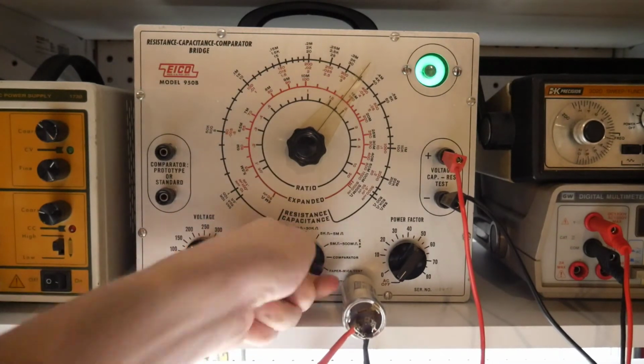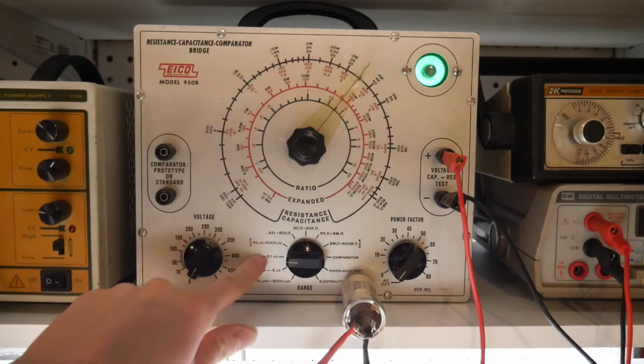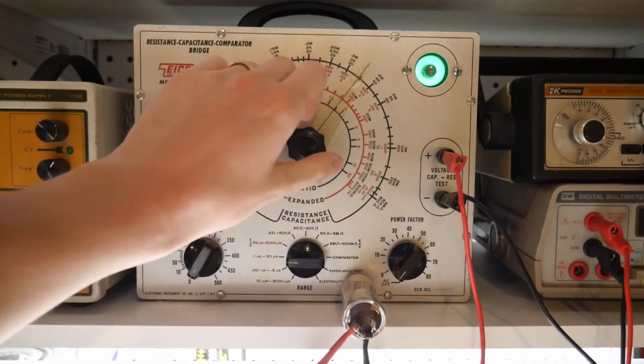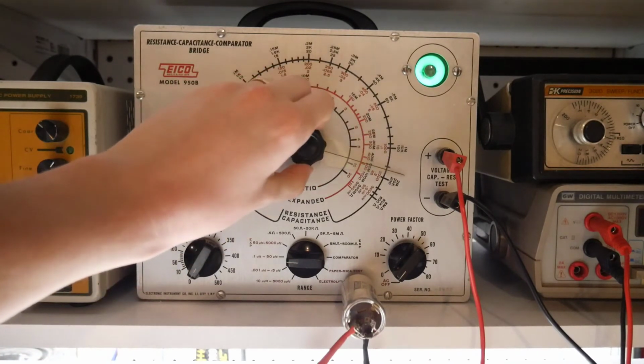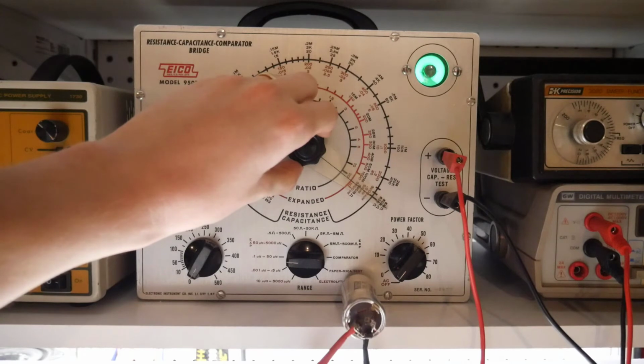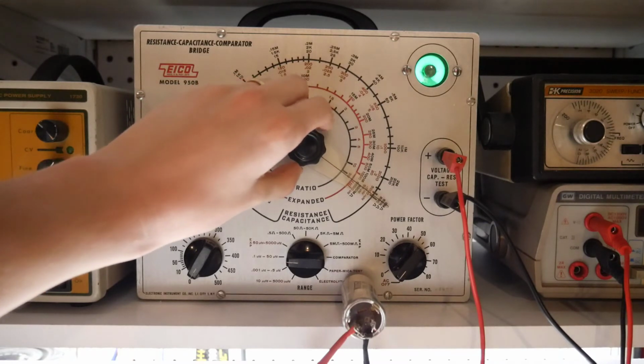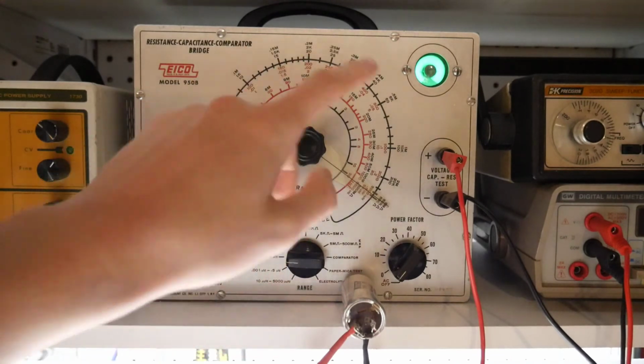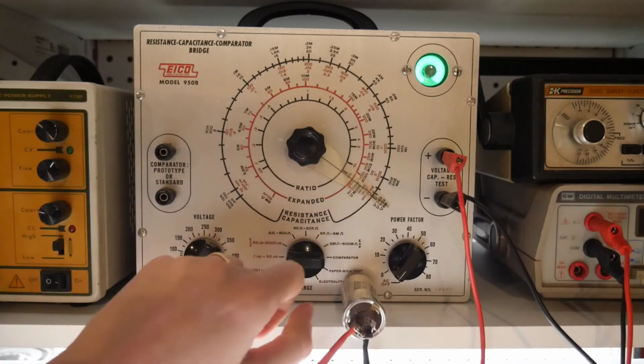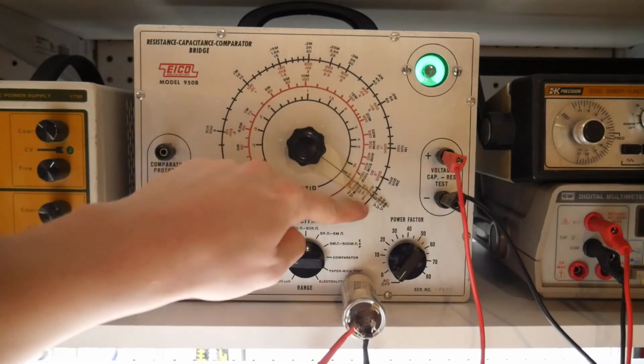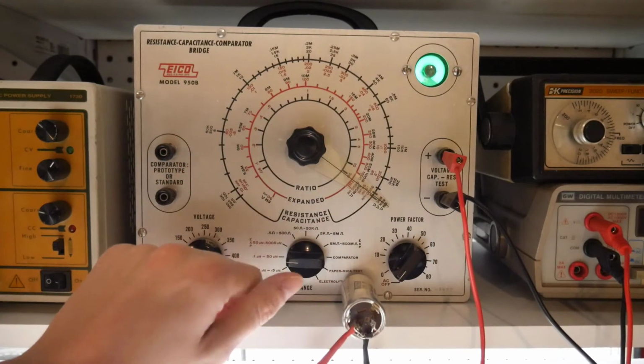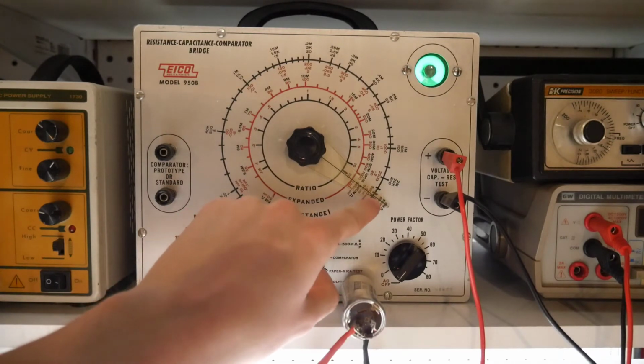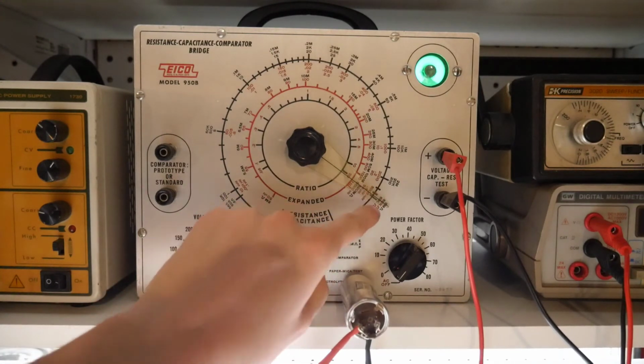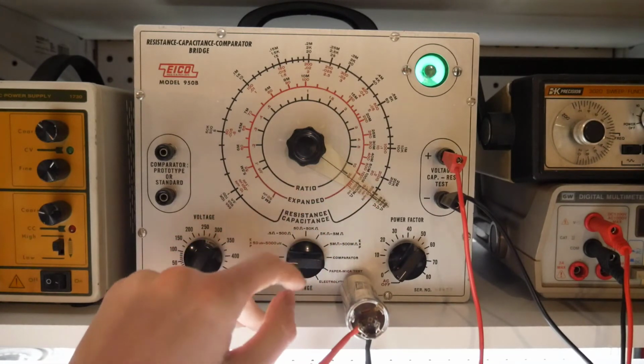So I'm going to test the capacitance first. Right there we're testing between 0.1 to 50 microfarads, and the way this works is you move your dial until you see that open and close. You basically try to get it to its widest point, and that is your capacitance value. Now this one takes some getting used to read, but right there, there are 3 tick marks, and this bottom one, according to the range we're set on, is 50 microfarads. So this is almost 50 microfarads. The one right before it would be 40, so this is, I'd say, about 47 or so microfarad.